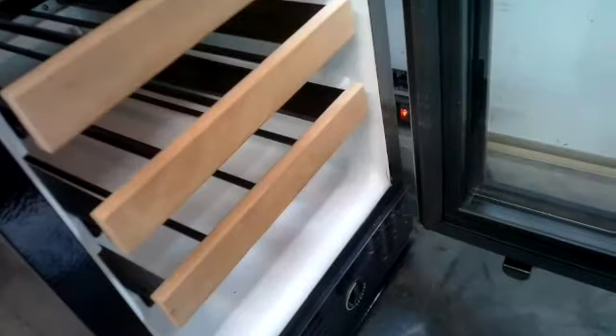Now the serial tag says it takes 2.75 ounces. However, this is a different evaporator and heat exchanger, so I'm not quite sure if that's going to be the right amount. So I'm just going to charge it and check the superheat on it, make sure that we don't have a frost back, and I'll check the temperature inside when you get it running. I'll also check that the shelves are all working properly and they're not hitting the back plate. So we got clearance there.